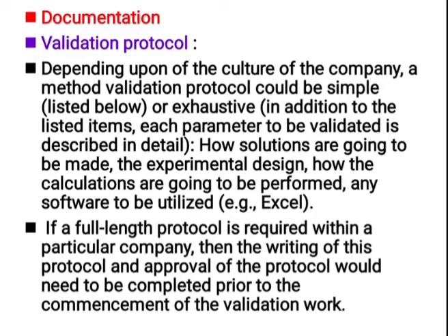Then if a full length protocol is required within a particular company, then the writing of this protocol and approval of the protocol would need to be completed prior to the commencement of the validation work. It means simply, if any company requires a full length protocol, a complete protocol, then the writing and the approval of this protocol would need to be completed prior to the commencement of the validation work.